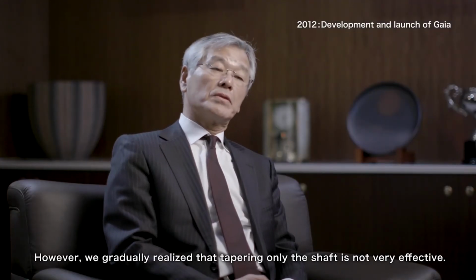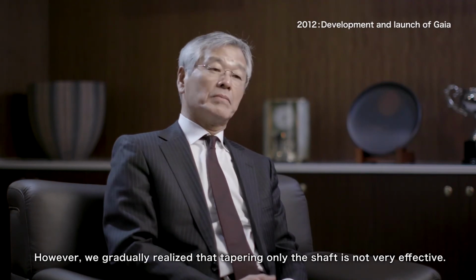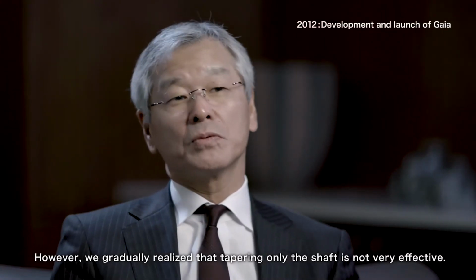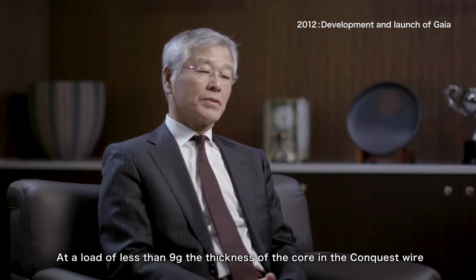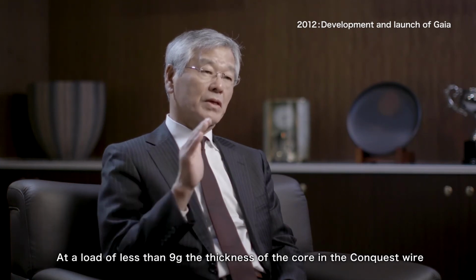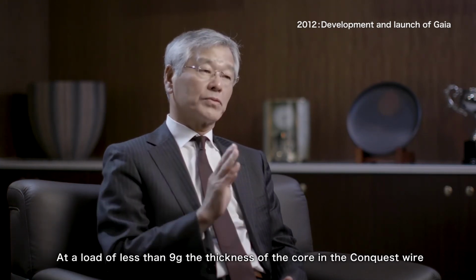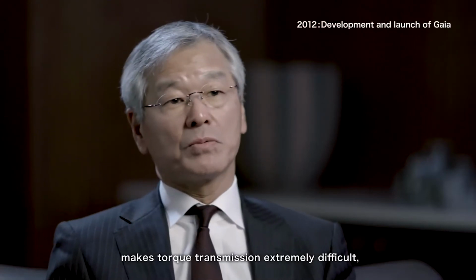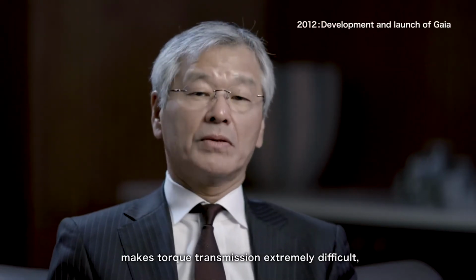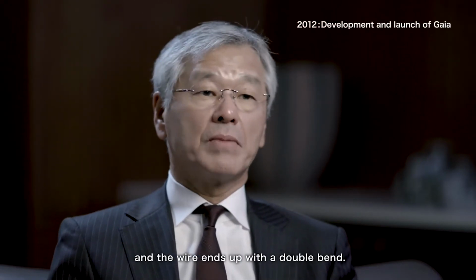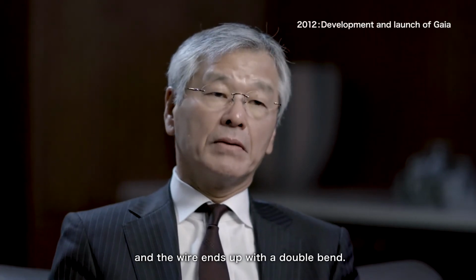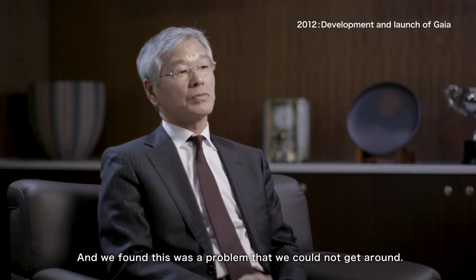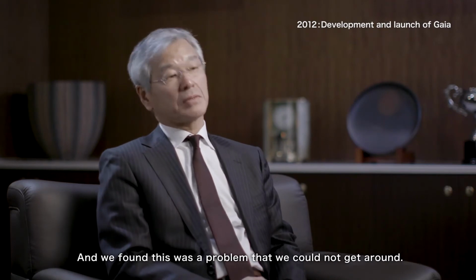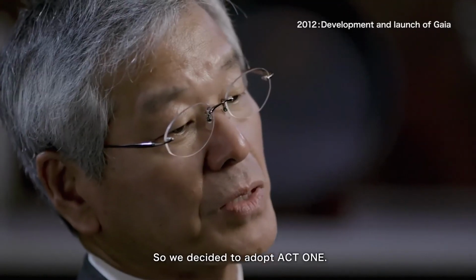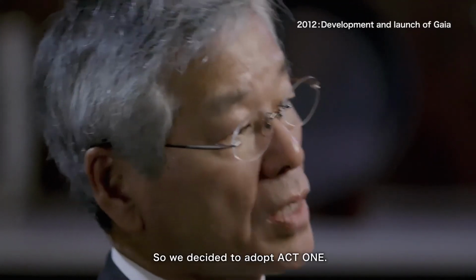However, we gradually realized that tapering only the shaft is not very effective. At a load of less than 9 grams, the thickness of the core in the Conquest wire makes torque transmission extremely difficult, and the wire ends up with a double bend. We found this was a problem we could not get around. So we decided to adopt Act 1.